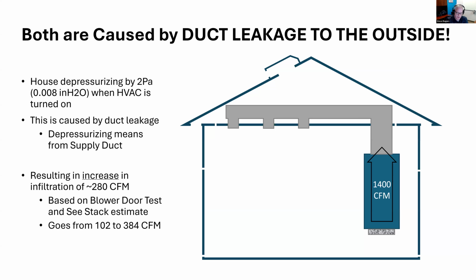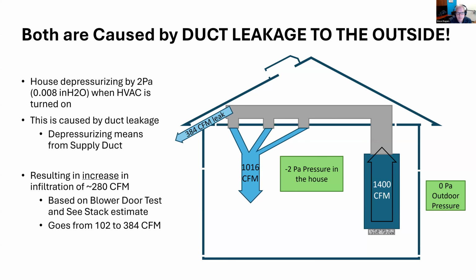Anytime there's ductwork in the attic, let's say we've got a system in a closet that's inside the house and it's moving 1,400 CFM, let's say it's a 3.5-ton system. But there's leakage, and so only a little over 1,000 of that 1,400 CFM is coming back into the house, with the remaining 400-ish CFM leaking into the attic and then falling out the soffit vents or going out the ridge vent. It's probably heavier than the air that's in there, because it's cold air. But when that happens, there's something important that happens, and that is it's not just that you lost like a quarter of the airflow. It also caused a pressure imbalance.